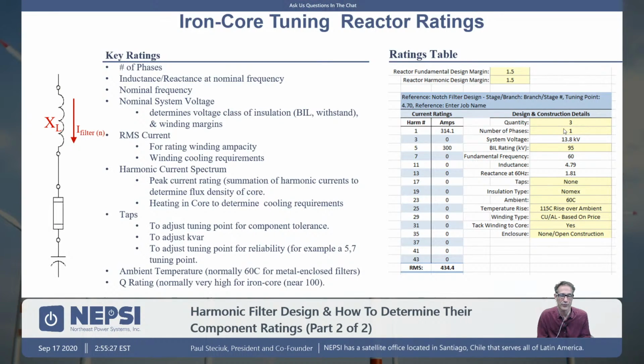We're specifying quantity. Do we want single-phase reactors or three-phase reactors? Typically, NEPSI is only supplying three-phase reactors up to the 15 kV level. That would be most of our designs. We will not go with three-phase reactors above that voltage level. Specify voltage: the reactor supplier wants to know what the system voltage is. That helps them to determine the insulation level. We want the BIL level of the reactor, the withstand voltage of the reactor, and then finally the inductance of the reactor at either 50 or 60 hertz, depending upon the fundamental frequency.